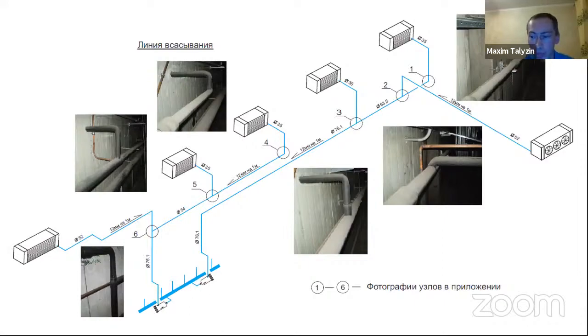when the temperature decreases and the solenoid valve or electronic expansion valve closes, we have a number of liquid in each evaporator. And because the pressure is higher at this point, all liquid goes to the header and then goes to the compressor. And that's the reason why we have lack of lubrication. And just after that, this case was closed. So thank you for attention. My example just highlights what Trevor said, and why understanding of the compressor is very important to find the real failure of a refrigeration system.